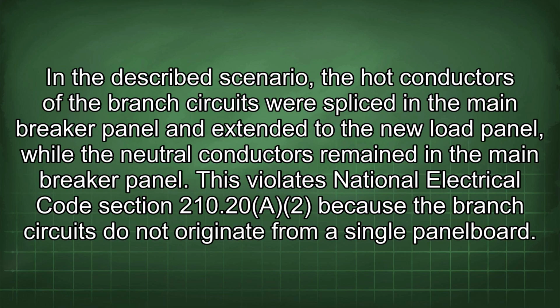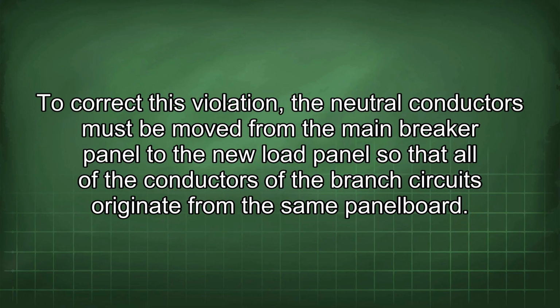In the described scenario, the hot conductors of the branch circuits were spliced in the main breaker panel and extended to the new load panel, while the neutral conductors remained in the main breaker panel. This violates National Electrical Code Section 210.20(A) because the branch circuits do not originate from a single panelboard. To correct this violation, the neutral conductors must be moved from the main breaker panel to the new load panel so that all of the conductors of the branch circuits originate from the same panelboard.